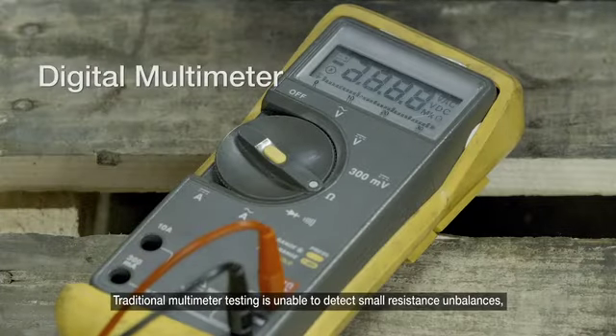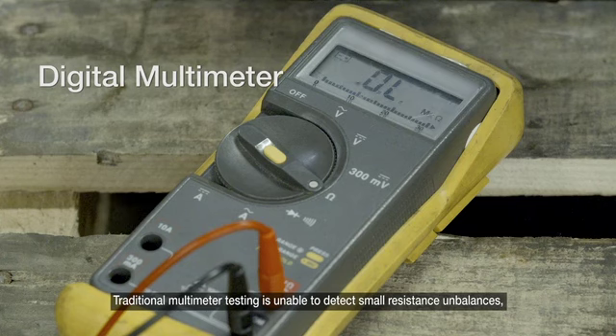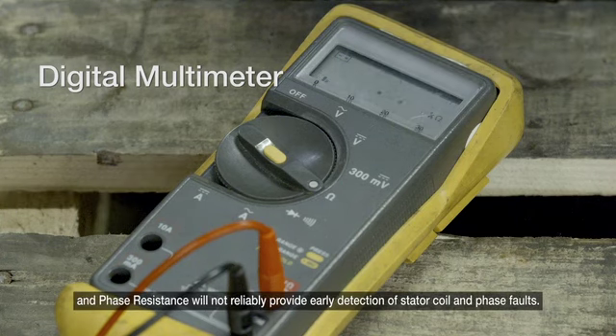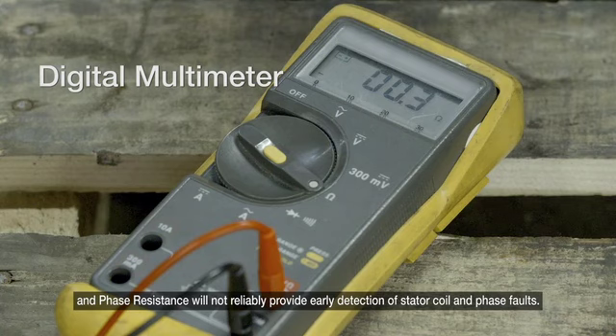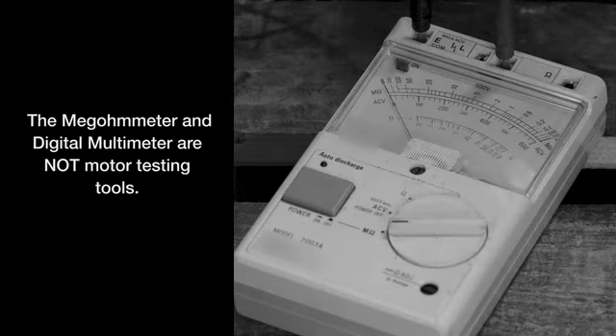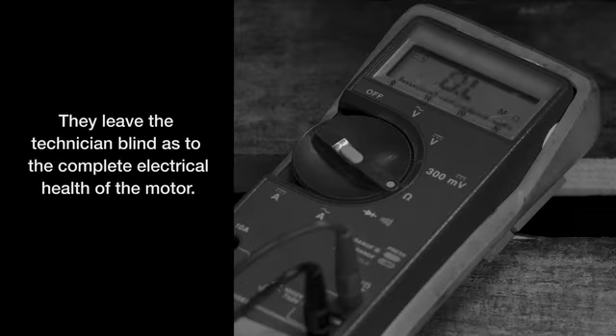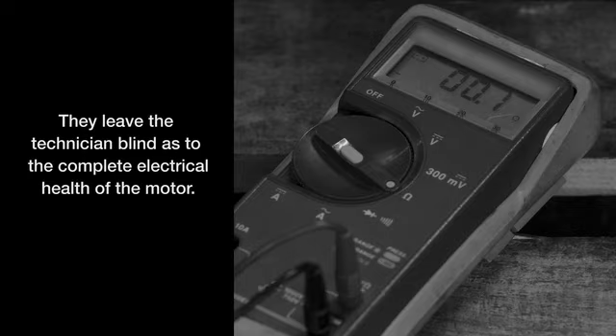Traditional multimeter testing is unable to detect small resistance unbalances, and phase resistance will not reliably provide early detection of stator coil and phase faults. The megohmmeter and digital multimeter are not motor testing tools. They leave the technician blind as to the complete electrical health of the motor.